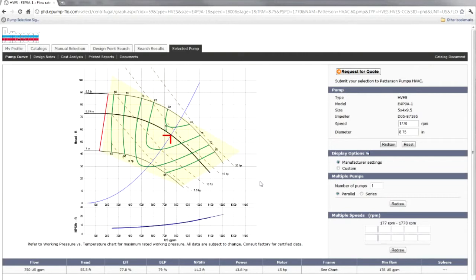It looked good on the curve. Or do you want to save the money on the pump, get a smaller pump, and have it operate slightly less efficiently? These are things that have to be evaluated. The reason this pump is further out to the right is because it's got smaller connections. It's only a 5x4. You go into a larger pump and it's going to pull you further to the left. This pump is slightly to the right. The bigger pump is slightly to the left. That means that we have a bigger pump for the application. Here we have a smaller pump for that application.